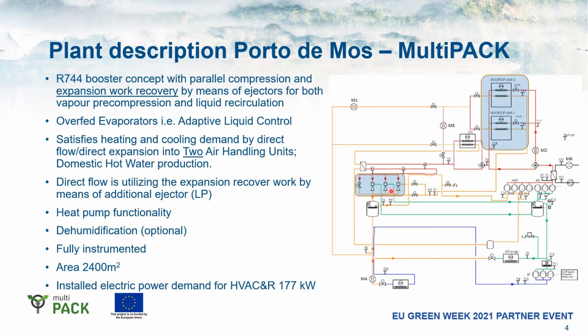What is a bit special here, beside the ejectors, is that the system is fully integrated also in terms of air handling, air conditioning and heating. So we satisfy the heating and cooling demand directly with dedicated air handling units which are sitting on the roof of the building. Here we have direct evaporation of CO2 in the coils of the air handling units, or heat rejection also directly into the air handling units. What we also have included is domestic hot water production right after the compressor outlet of the medium temperature and auxiliary compressor train.